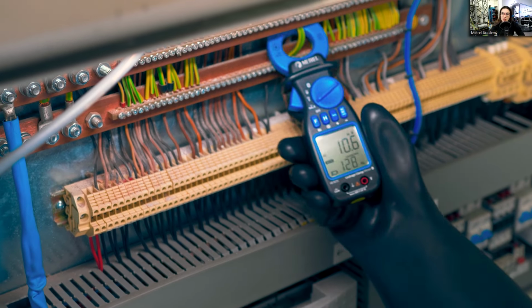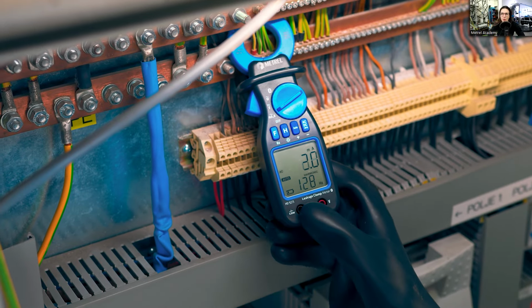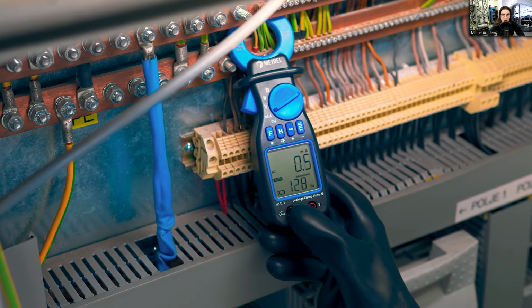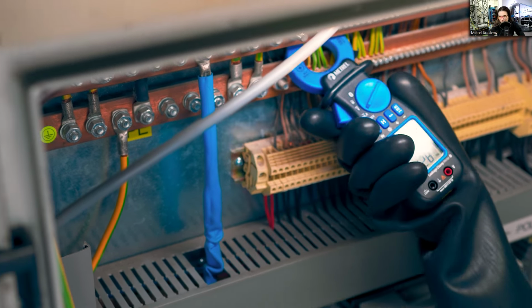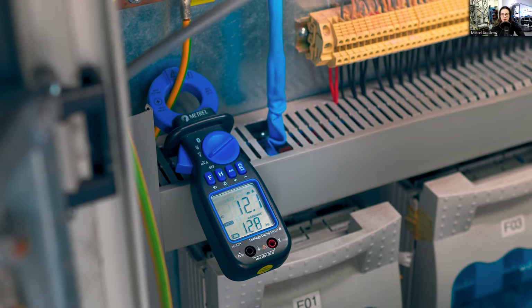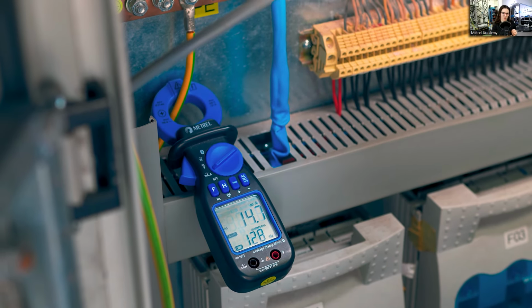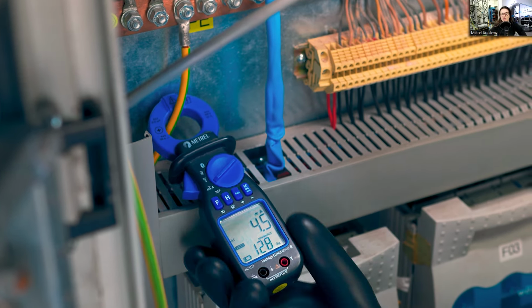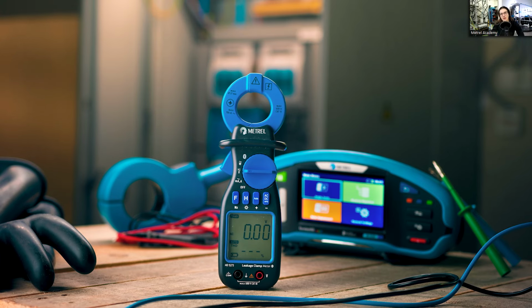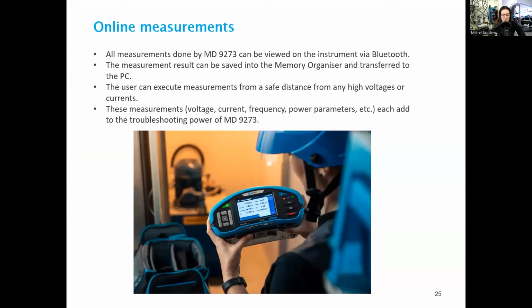Again, like with the leakage current measurements, we can firstly clamp multiple wires to look where our signal is flowing. And only when we find it, we can take a look at each wire separately. So this enables us to work faster. Once we find where the signal has gone, we know which part of the installation has the installation problem. Another thing that has to be mentioned: while we do need both the instrument and the clamp for this method, they do not need to be connected over Bluetooth in this case. We only need to have them both, but separate.